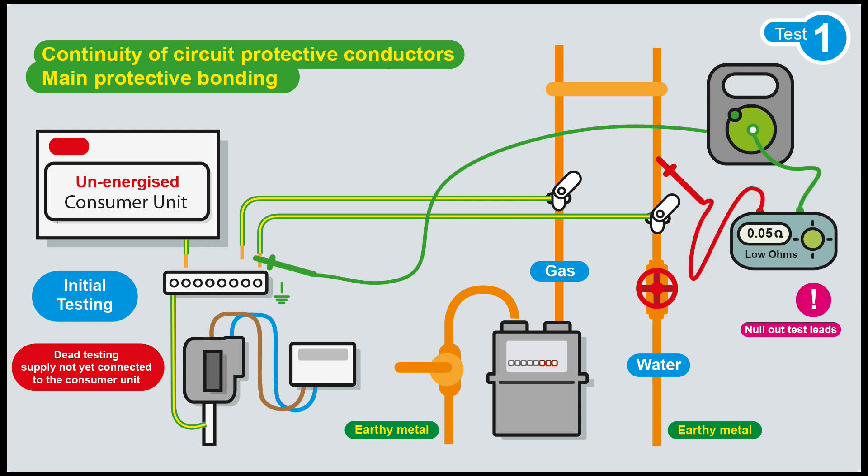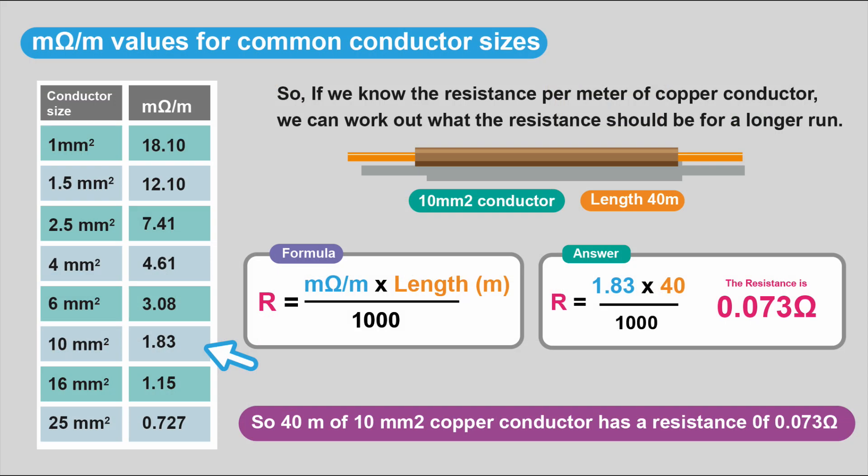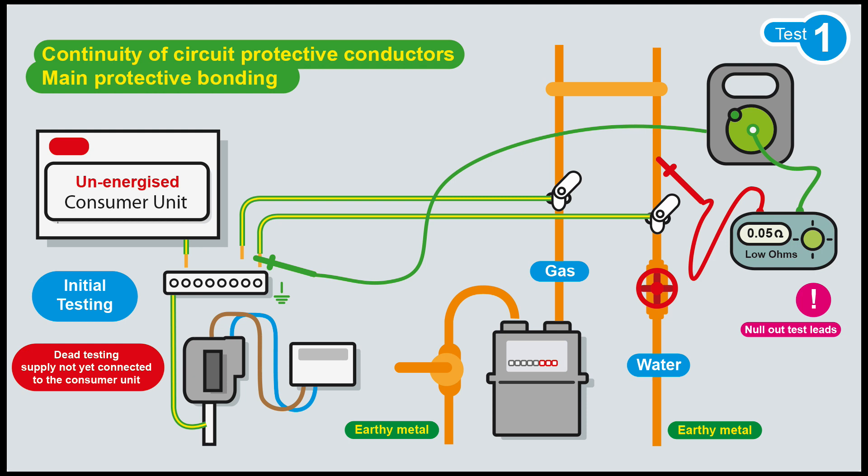Nobody's quite sure where that number comes from, to be honest, but that's the guidance that we're being given. Remember in the previous example, we got 0.073 ohms, and that was for 40 meters of 10 mil conductor. So if it needs to be less than 0.05, we know that 40 meters is going to be too long.